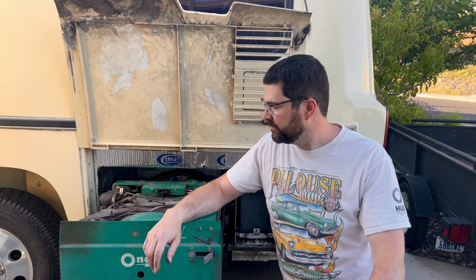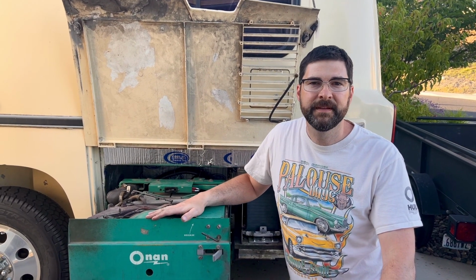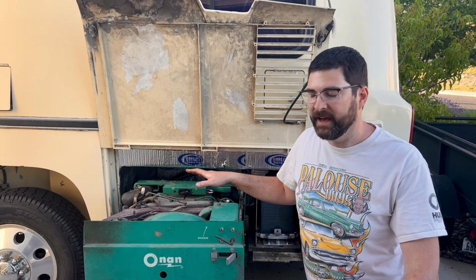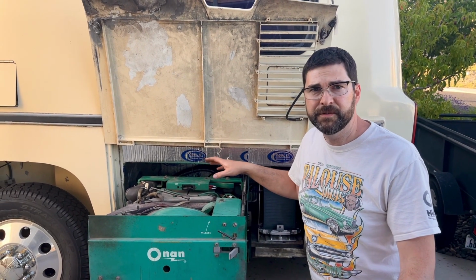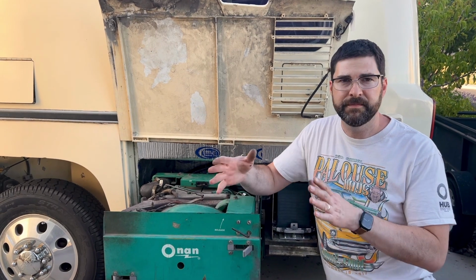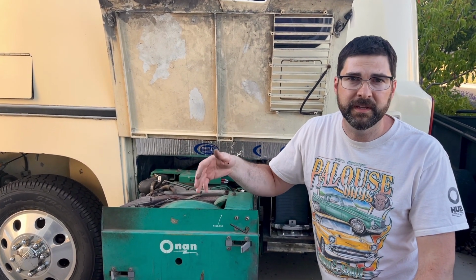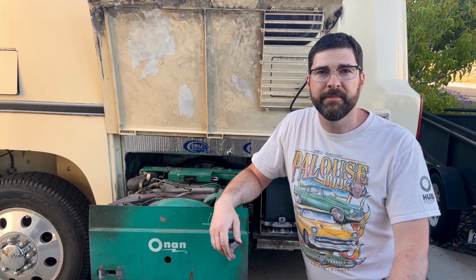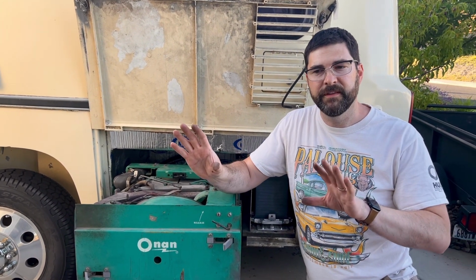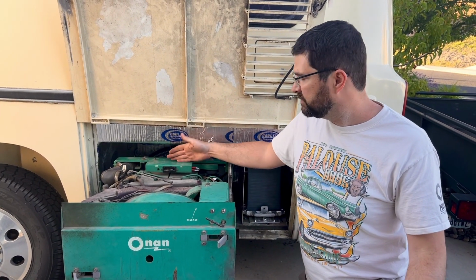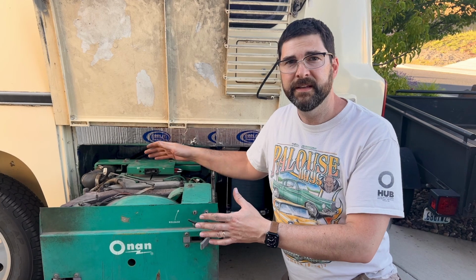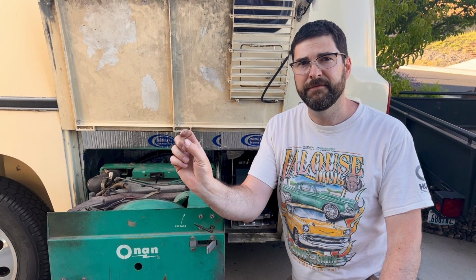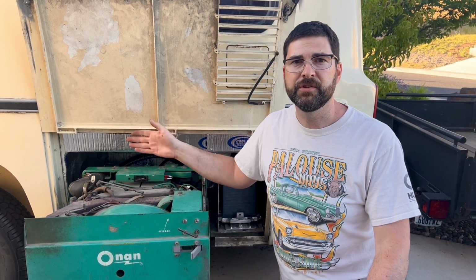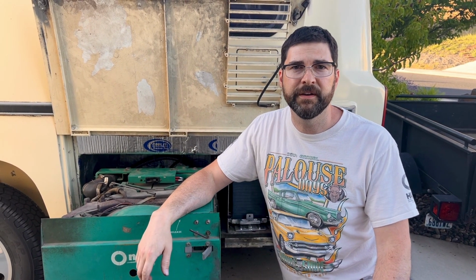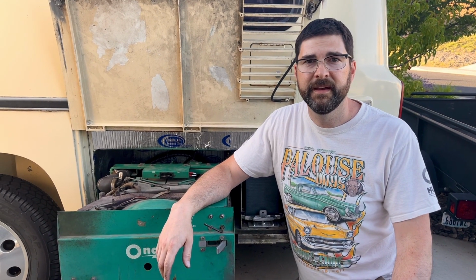Okay, so we've got everything hooked up, all the wiring done. We had to do a little cable management because I didn't hook things up exactly the way they were, with the strain relief and things like that. I ended up needing to make sure things were routed around the back of the generator. It turns out the back of the generator, when it's all the way in, is only about 1.5 inches off the back wall, so I had to make sure all my conduit and control wiring were out of the way.